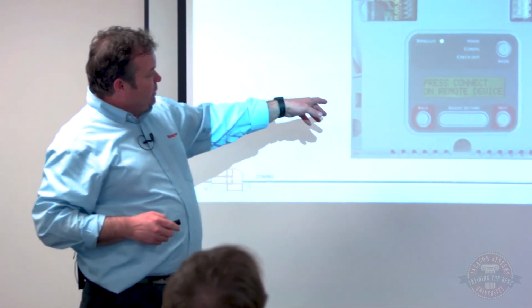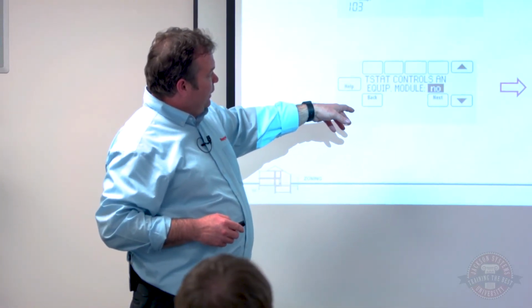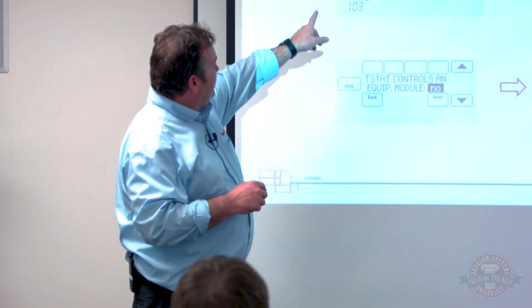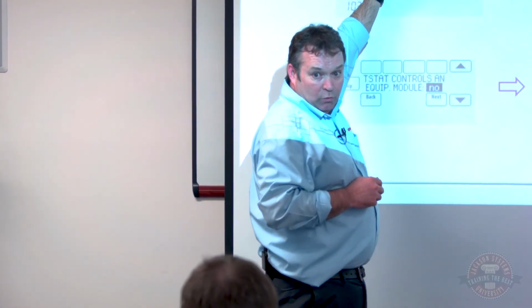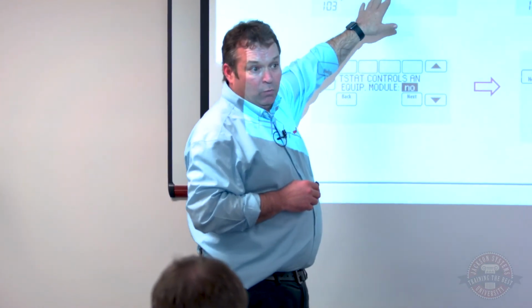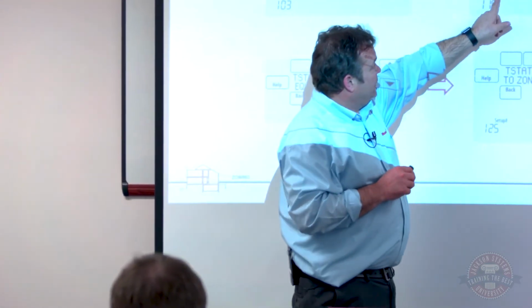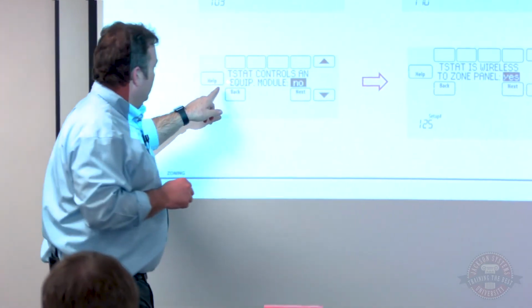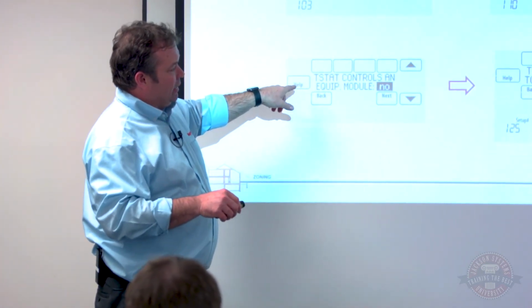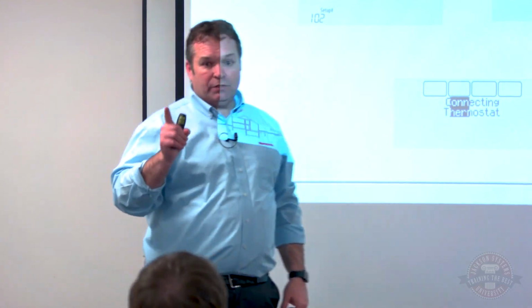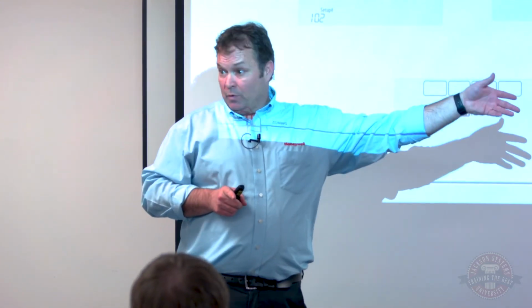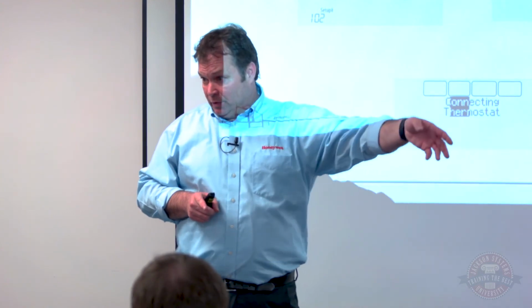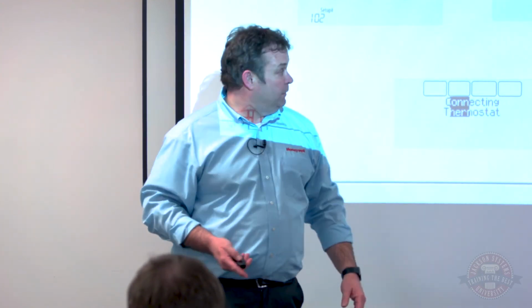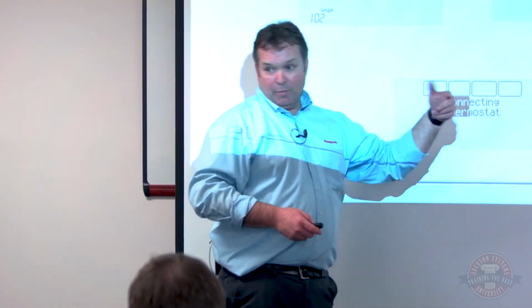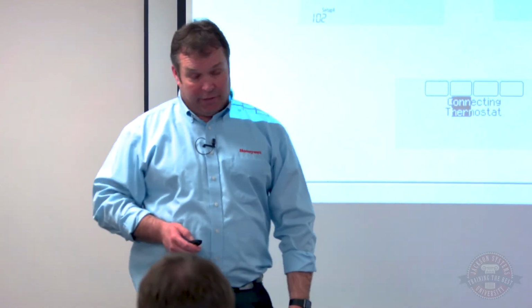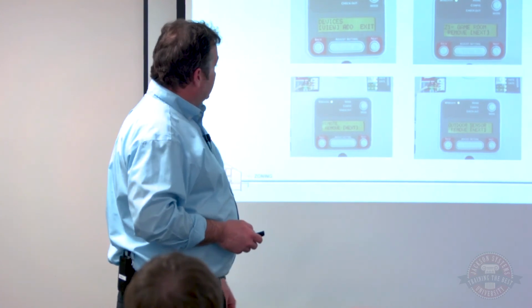Then I can check out my system by going in here and setting my thermostat up. It'll roll through a bunch of names, and I can pick what I want to call that zone, then it asks if I'm zoned, and I say yes. Equipment module, yes or no? I'll say no, I've got a zone panel. Then it'll ask which zone this damper is - zone 1, zone 2, zone 3 - and I'll address it accordingly. Then I say connect, it hooks my thermostat up, and I'm done.